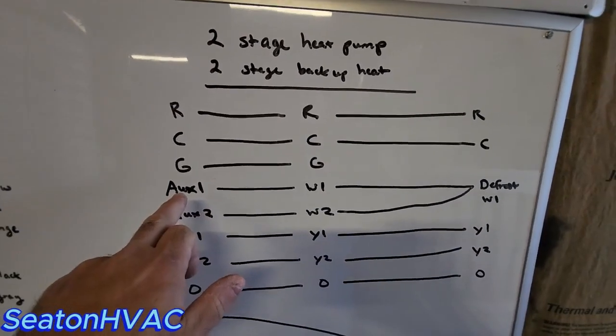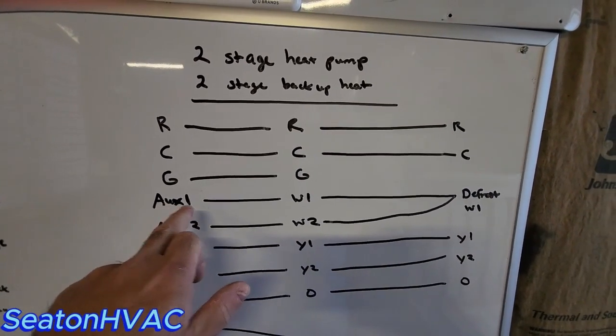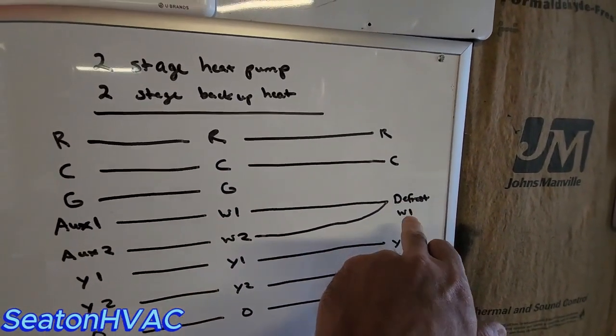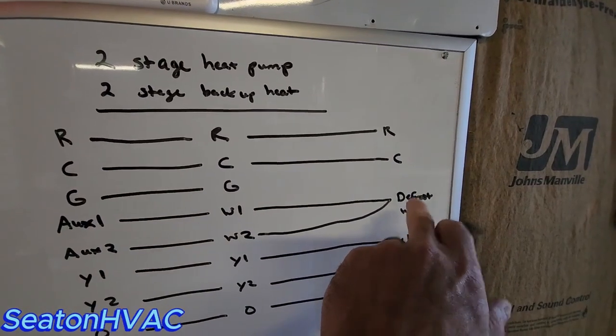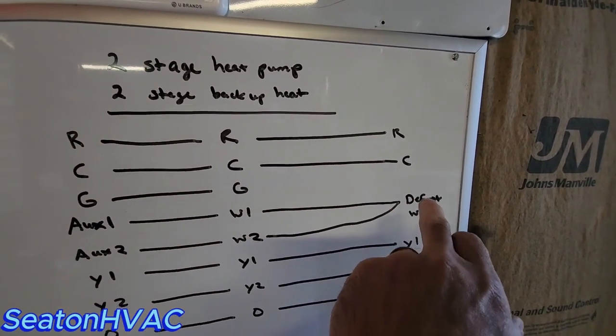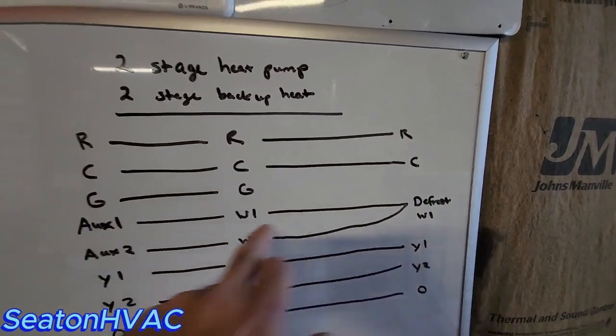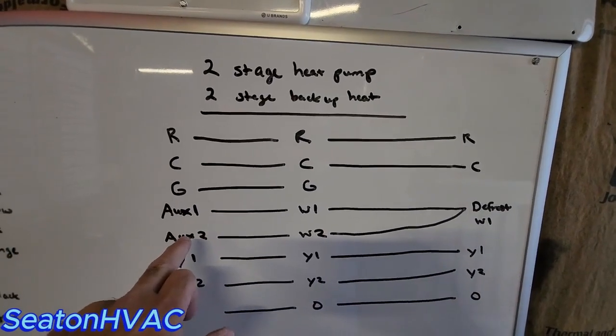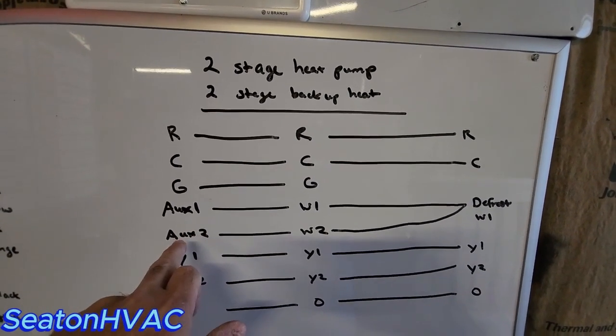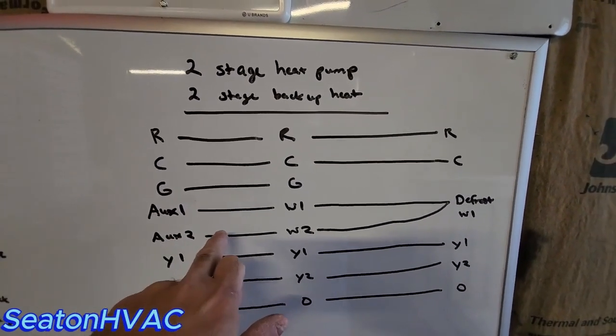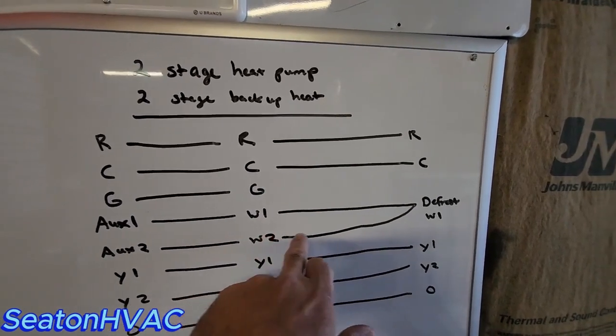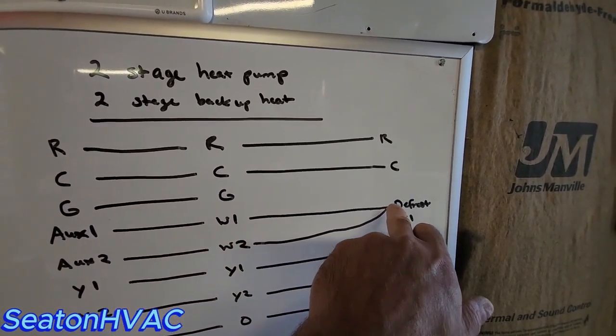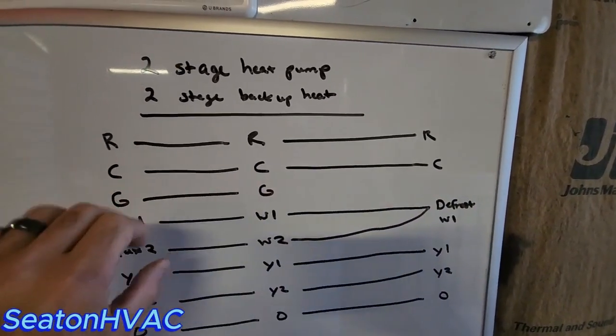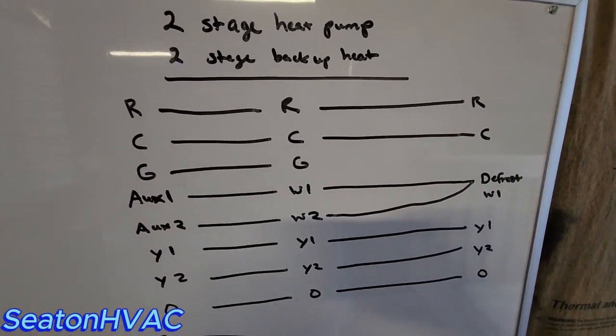Then you have your auxiliary, your backup heat, stage 1, out to your W1 outside. Usually there's only going to be 1 outside. I've never seen a heat pump that has 2 of them. And then auxiliary 2, so that would be, let's say, your second stage of backup heat, okay? You would tie that just indoor, and then you would wire them all outside, because you want to energize your whole bank of heat strips when it goes into defrost.